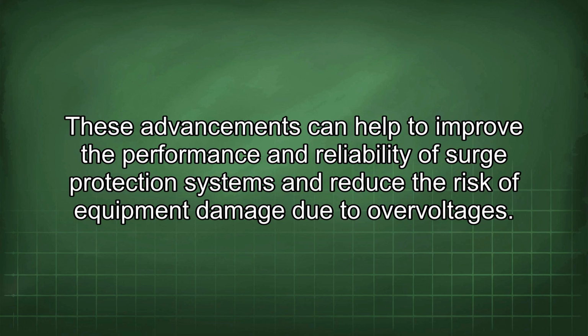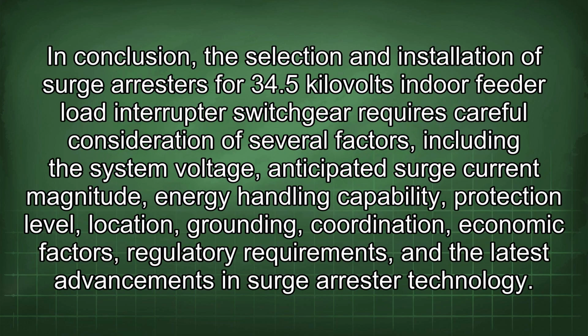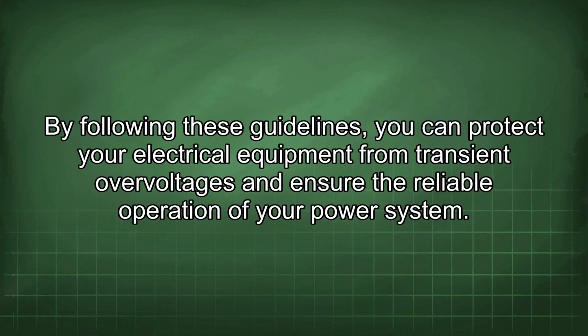In conclusion, the selection and installation of surge arresters for 34.5 kV indoor feeder load interrupter switchgear requires careful consideration of several factors, including the system voltage, anticipated surge current magnitude, energy handling capability, protection level, location, grounding, coordination, economic factors, regulatory requirements, and the latest advancements in surge arrestor technology. By following these guidelines, you can protect your electrical equipment from transient overvoltages and ensure the reliable operation of your power system.